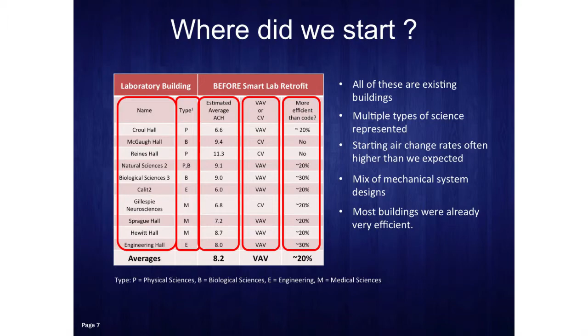They all had an estimated air change rate we thought was 6 air changes per hour. As Wendell told you earlier, those air changes had crept up over time, because we've come in and added snorkels, gas cabinets, and similar things, and nobody said, let's reduce the general exhaust—they just added more supply air. So pretty soon your air change rates in those rooms creep up higher and higher.